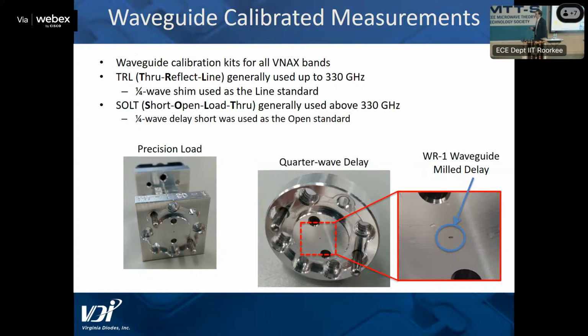And the reason is, for this line standard, that line is a quarter wave of waveguide. And the way you make a quarter wave of waveguide is you have a very thin, wafer-like shim with a rectangular hole cut through it. And that's your 90 degrees of waveguide. But of course, as the frequency goes up, the wavelength gets much smaller. So that shim becomes incredibly small, incredibly fragile. We do have quarter wave shims, and we do sometimes do TRL calibrations up to 1.1 terahertz. It's not something that you would want in a regular laboratory environment where it's being used a lot, because it just won't last very long.